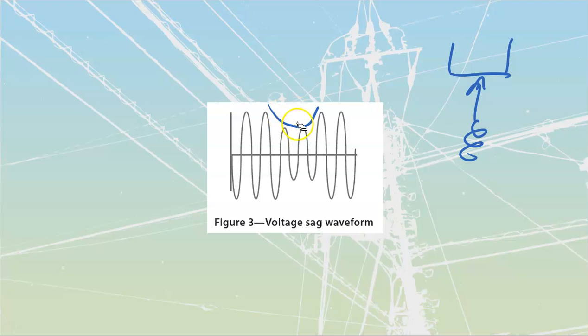Usually you can attenuate this by taking care of your large motors. All of those reduced voltage starters that we took a look at, auto transformer starting, wye delta starting, impedance starting, anything that's going to give us a reduced voltage is going to slow this down. Or if you go with a soft start or an adjustable speed drive, rather than just connecting across line to line and allowing this to drop, bring your motors on slowly. Usually this stuff is going to go away. If you do have sag you can't get rid of, then find the things that it's affecting, particularly computers, etc., and put those on an uninterruptible power supply so that they are not affected by it.